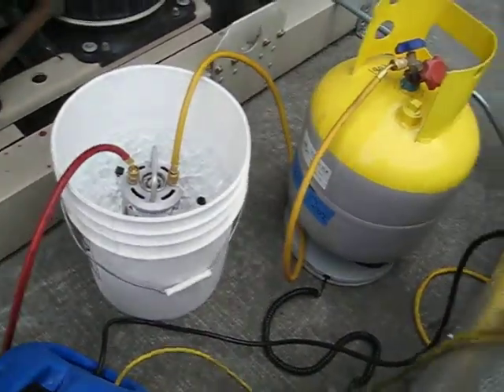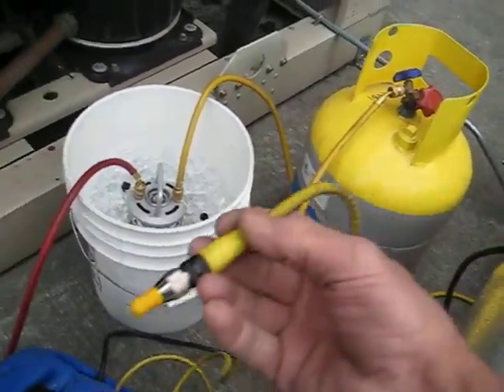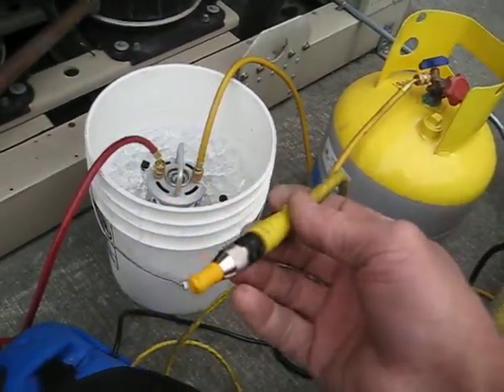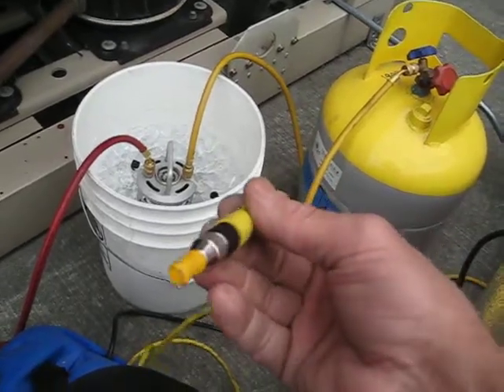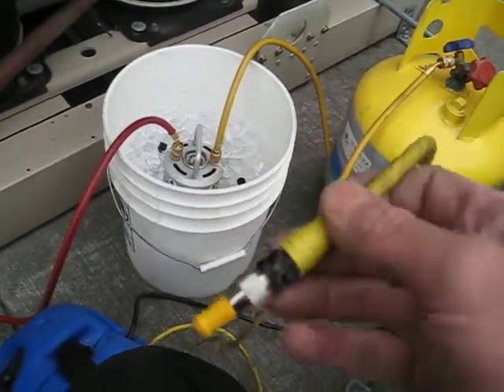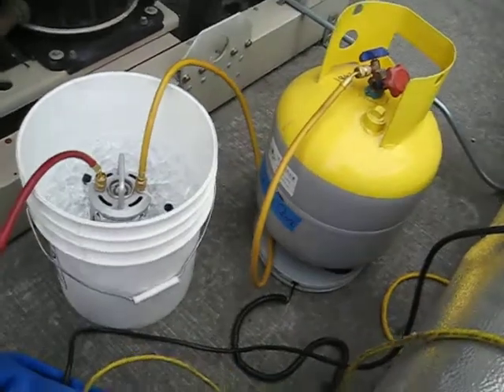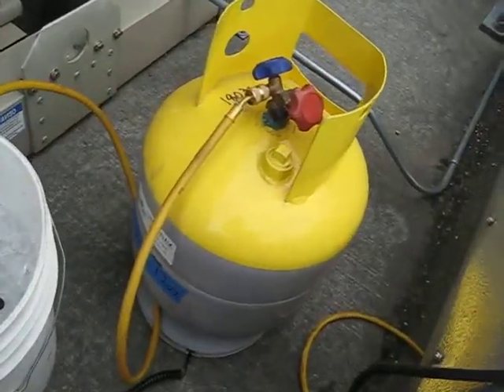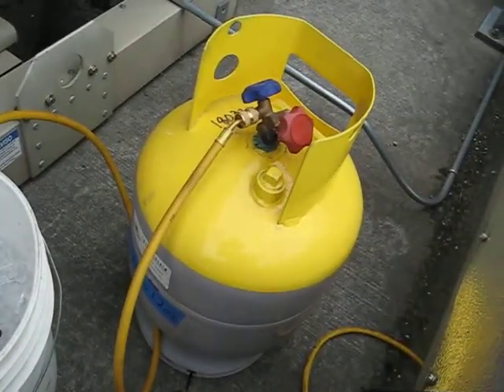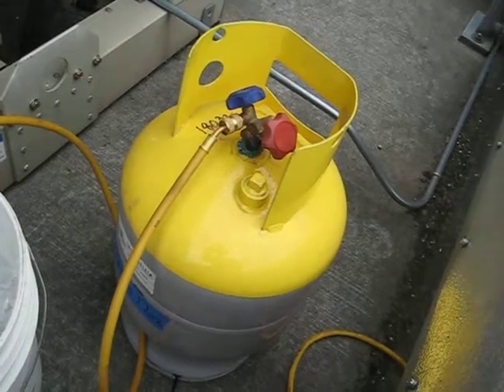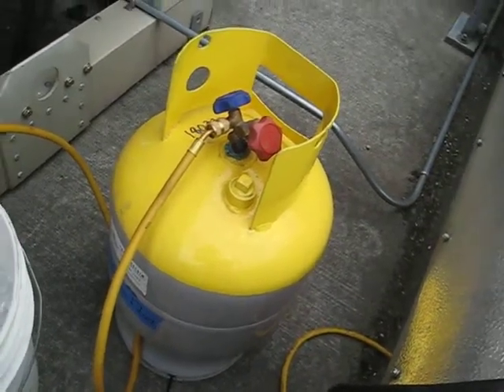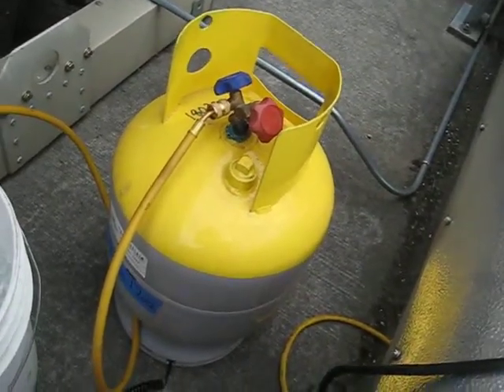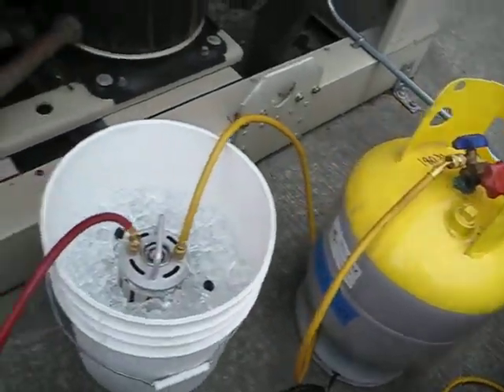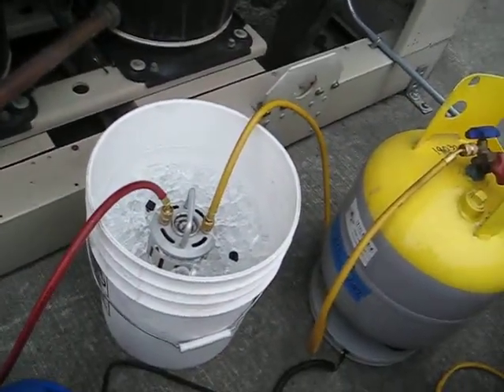I asked to get this one because it had this extra cord on it. If you have a float switch in a recovery bottle, you take out that little yellow end there. It's a little special plug. I noticed the main refrigerant guy, who takes care of all our bottles, was putting float switches in there. This one doesn't have a float switch, so you have to be careful when you're filling those, because you don't want to overfill it.